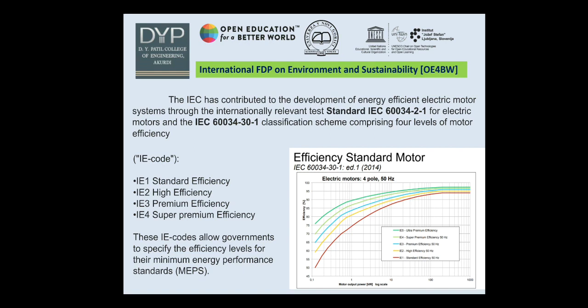Then the IEC, International Electrotechnical Commission, has contributed to the development of energy efficient electric motor systems through the internationally relevant test standard IEC 60034-2-1 for electric motors and the IEC 60034-30-1 classification scheme comprising 4 levels of motor efficiency. As we have seen in the last PPT, this IE code is divided into 4 efficiency levels. IE1 is standard efficiency as shown in the graph, IE2 high efficiency, IE3 premium efficiency, and IE4 super premium efficiency. These IE codes allow governments to specify the efficiency level for their minimum energy performance standard, that is MEPS.